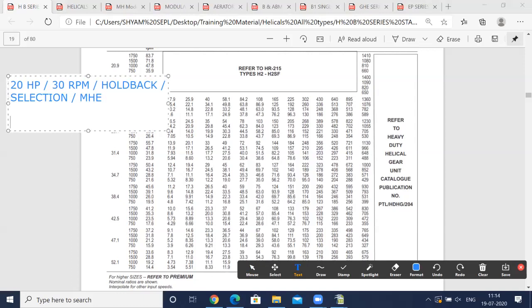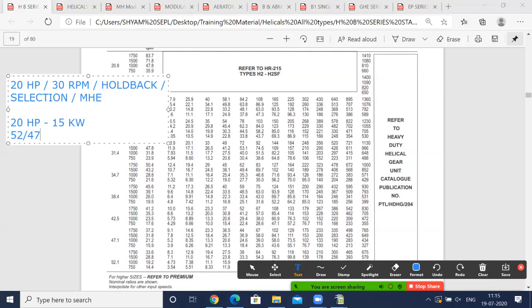So now, first of all, 20 HP you will convert to 15 kilowatt. 30 RPM means the ratio is around 52 or 47. What is available in the catalog? As you can see on this page itself, 47 and 52 both are available. Because what I did: motor kilowatt I assumed 15 kilowatt at 1440 RPM divided by 30 RPM, so that gives me 50. Now holdback. Why do you need a holdback? What is a holdback? That is another chapter which we will be discussing here. But let's first select the model, then we'll get back to the holdback part.